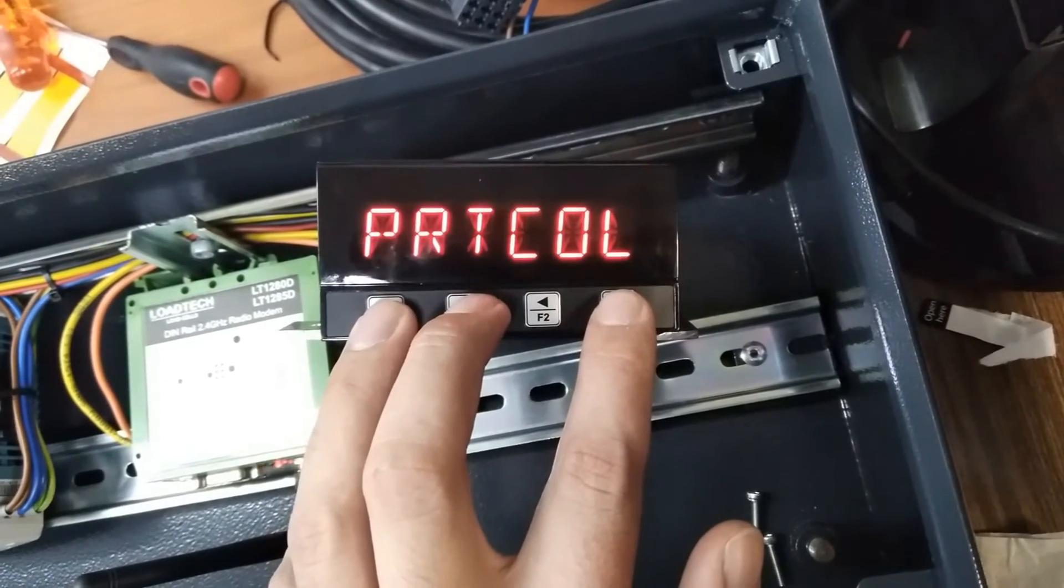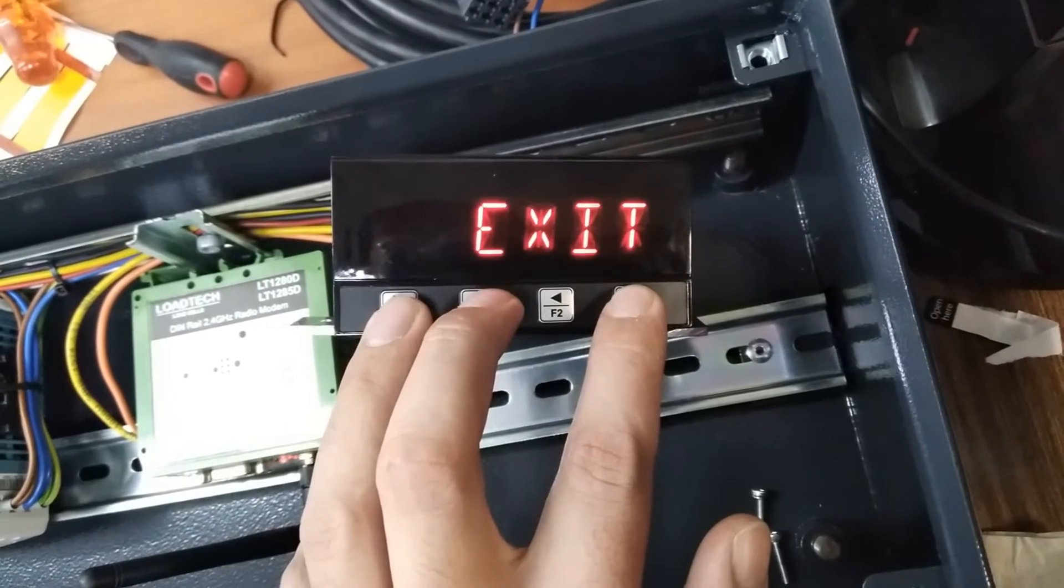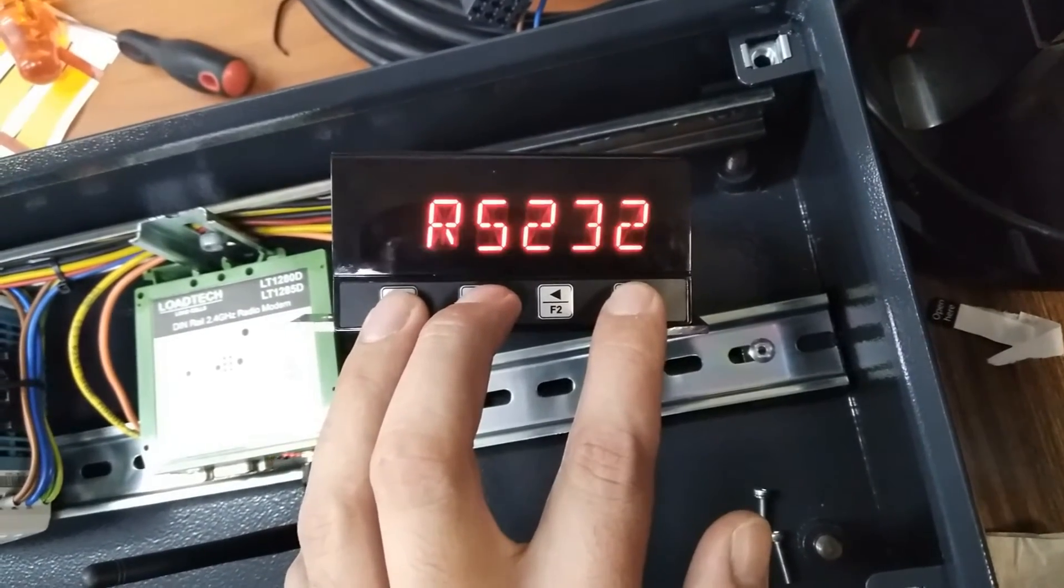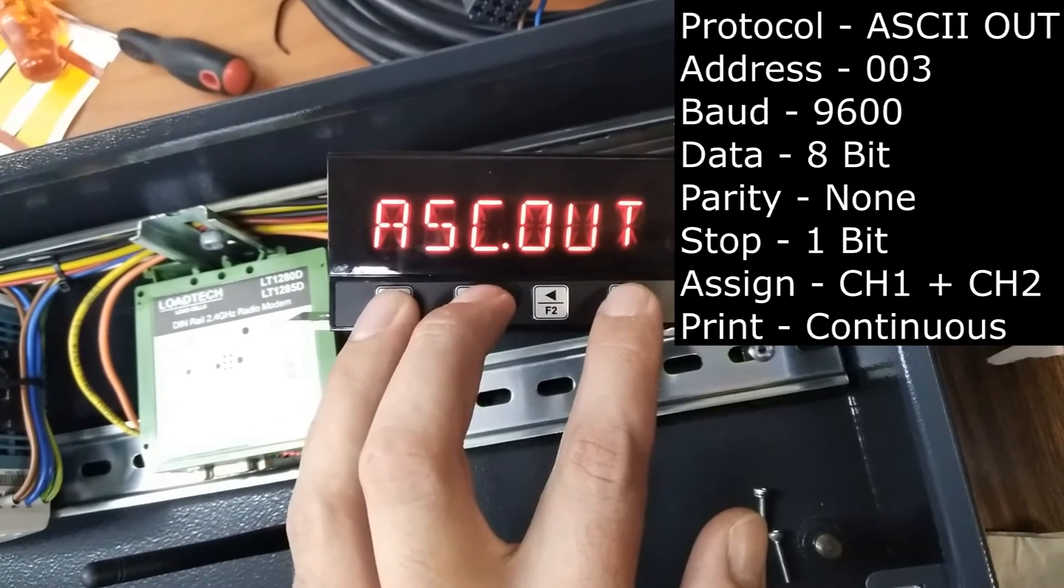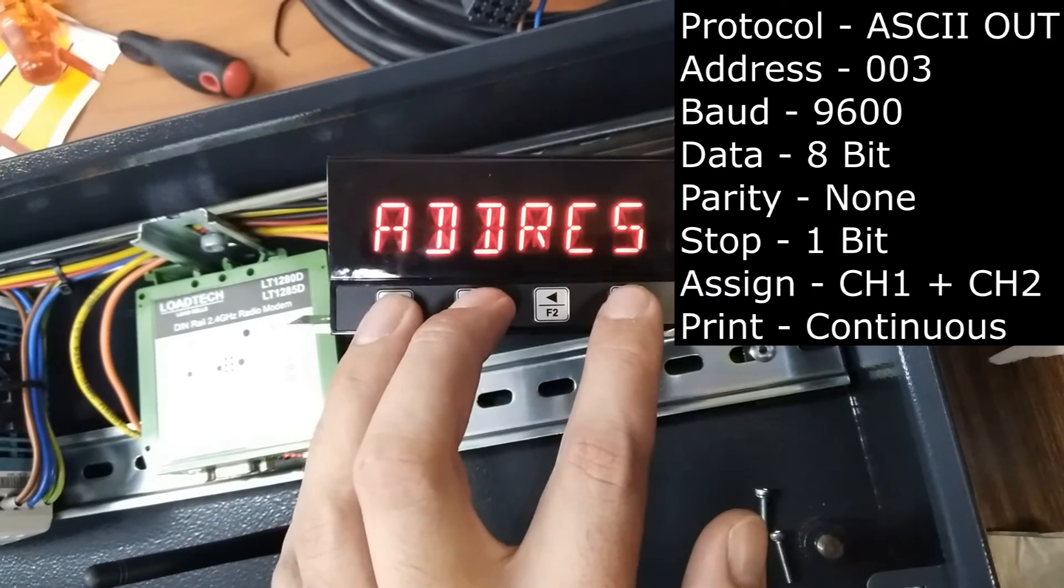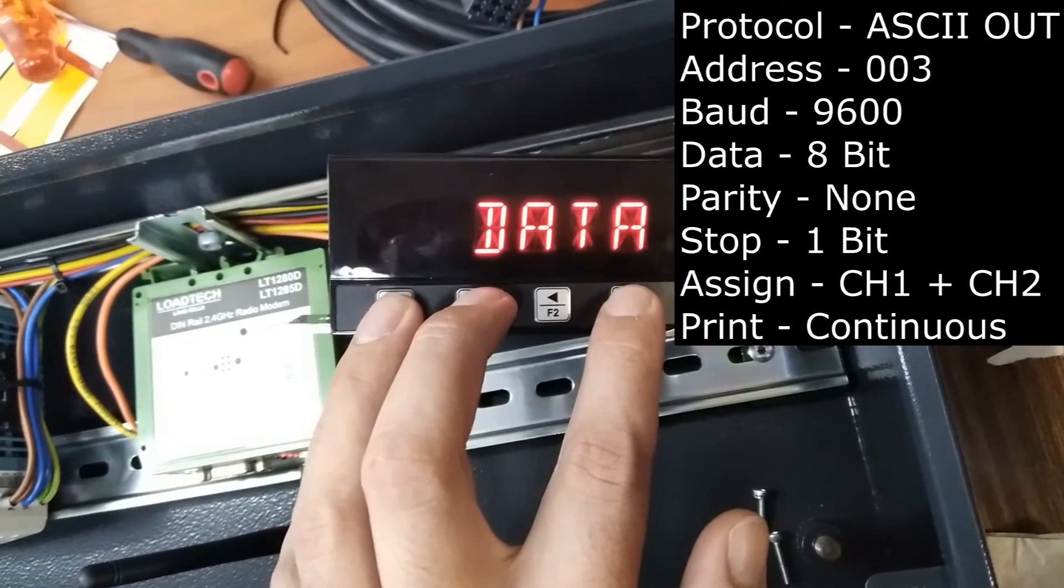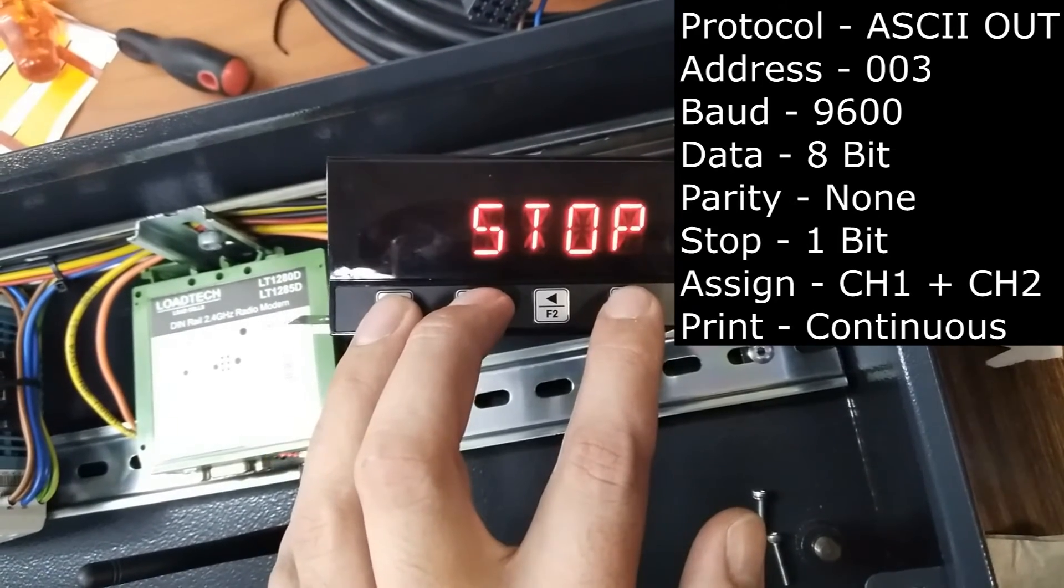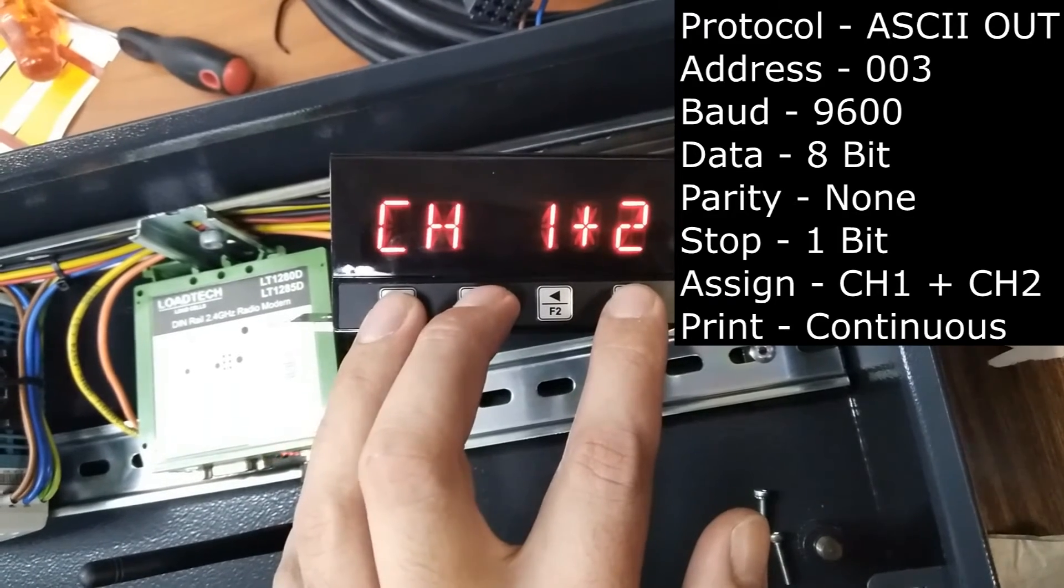Next, we're going to set up communication with the large display using RS-232. Your settings are on the screen as follows. Protocol will be ASCII out. Address, 003. Baud rate, 9600. Data, 8-bit. Parity, none. Stop, 1-bit. Assign channel 1 plus 2. And print, continuous.